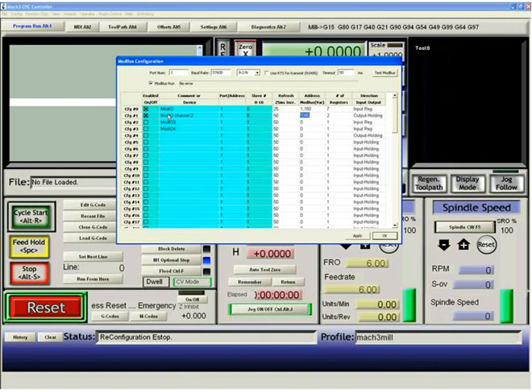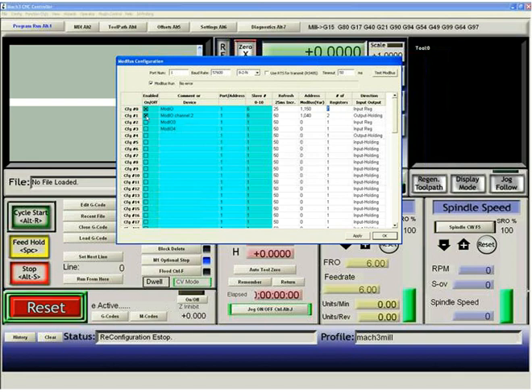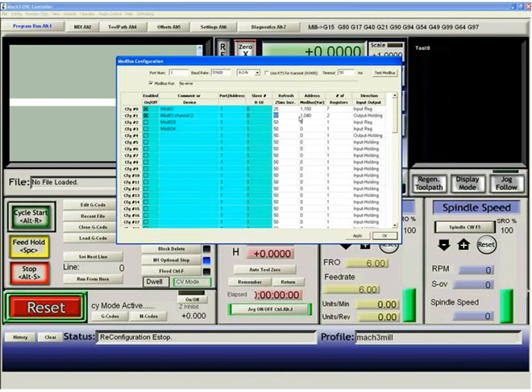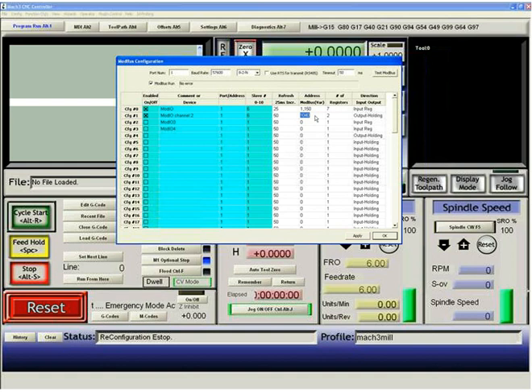So here we have, basically I'm doing two operations. Every 25 milliseconds, I'm sending seven registers from the PLC or Mod.io in this case, into configuration 0. And every 50 milliseconds, I'm sending two registers from configuration 1 to the Mod.io on address 1040.